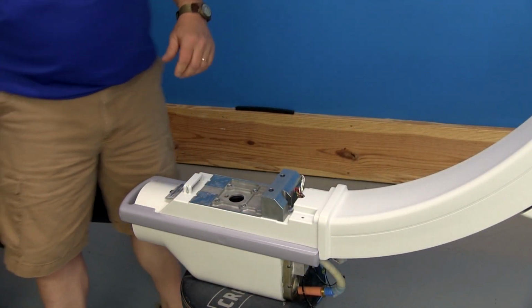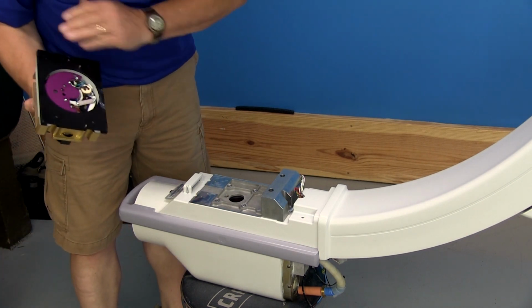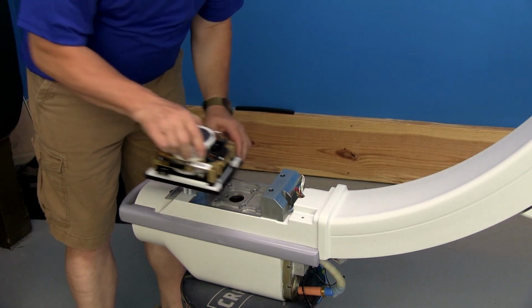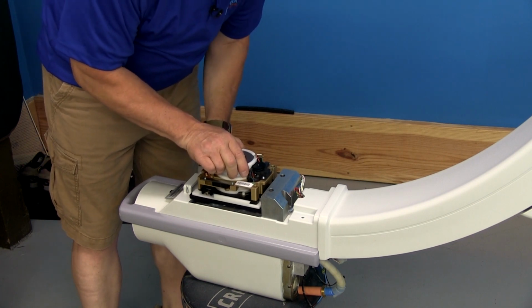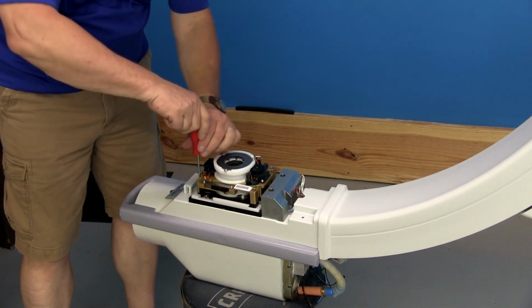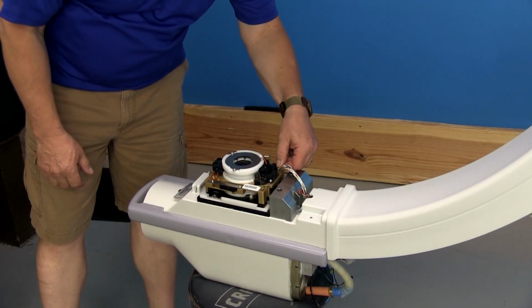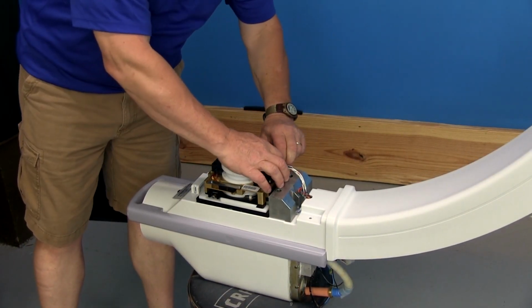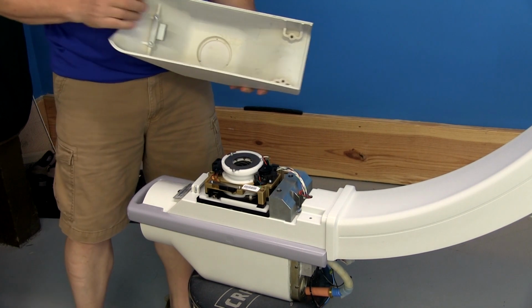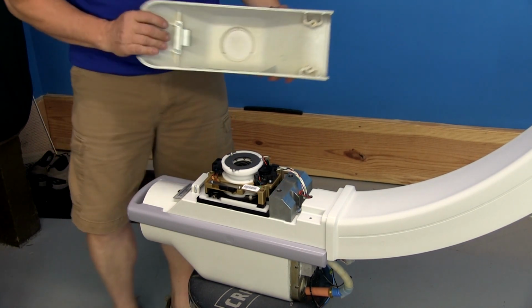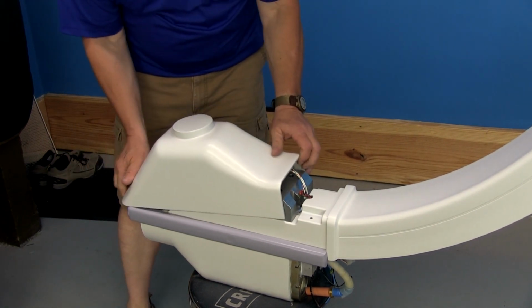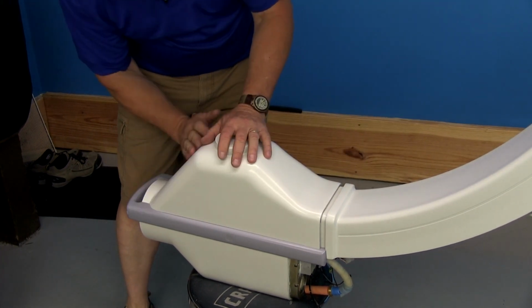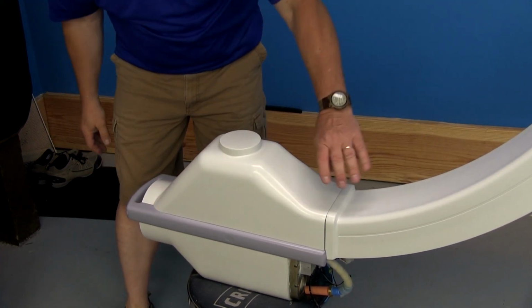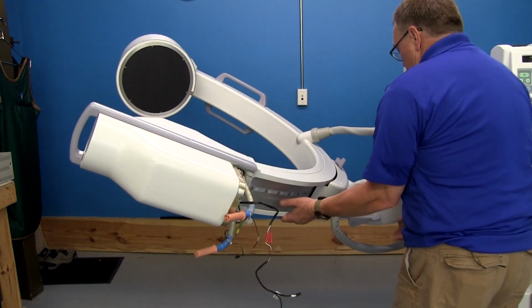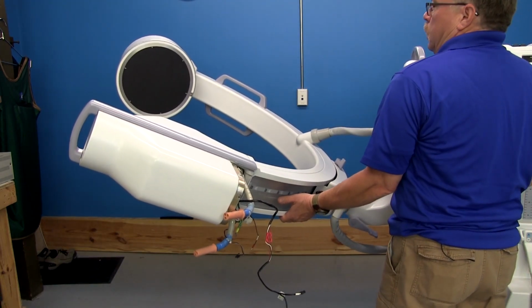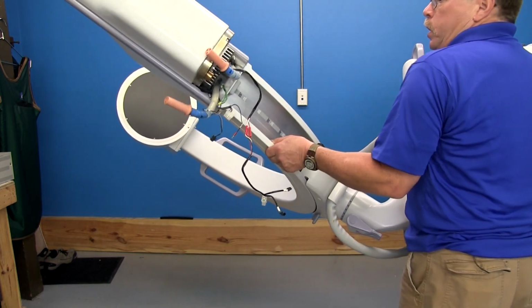Now we can reinstall the collimator. The collimator has a couple of alignment pins. You want to make sure you line them up with the holes. On your top cover, you have this bracket here that has to slide underneath this notch. So we lay it on and push it back, and then I'm going to roll this C back up so we can access the HV cables.